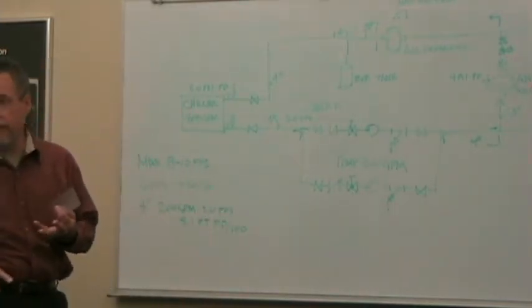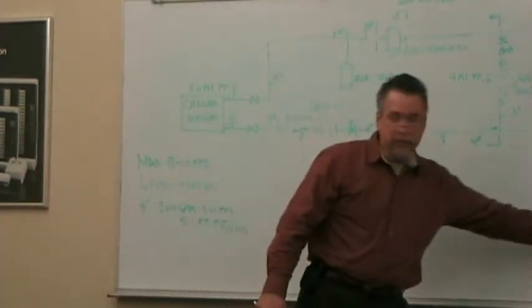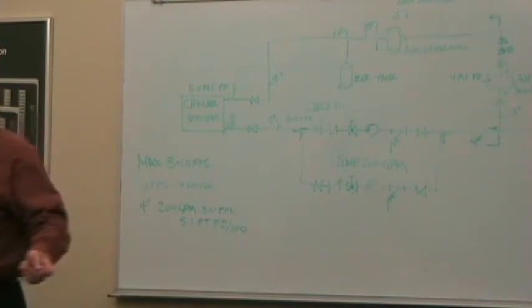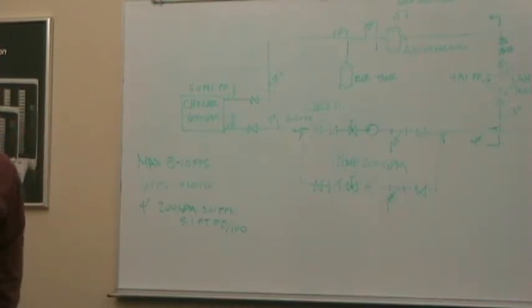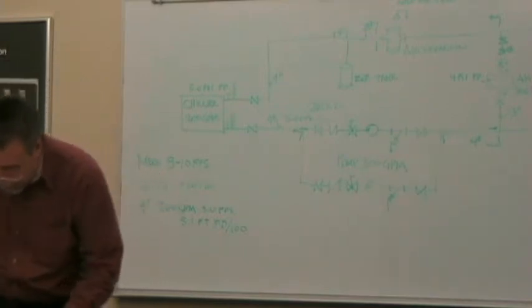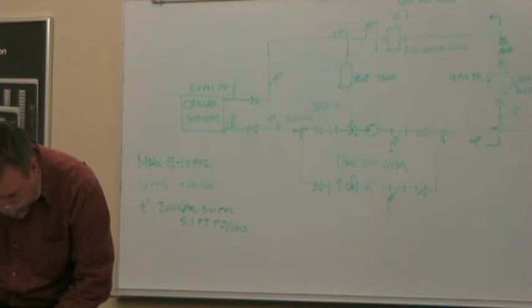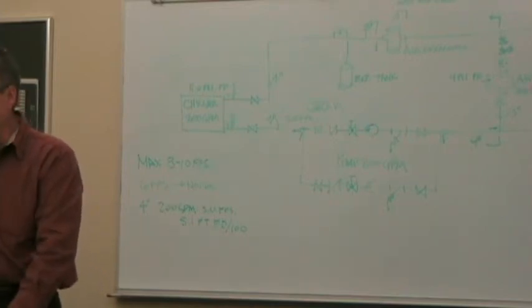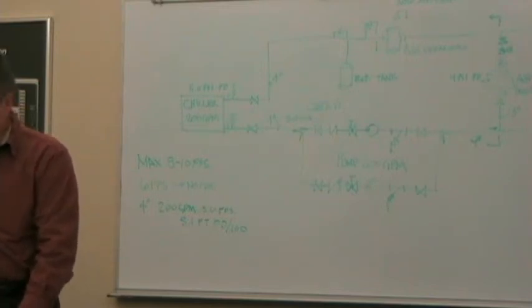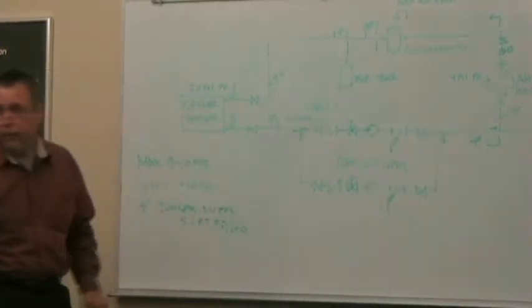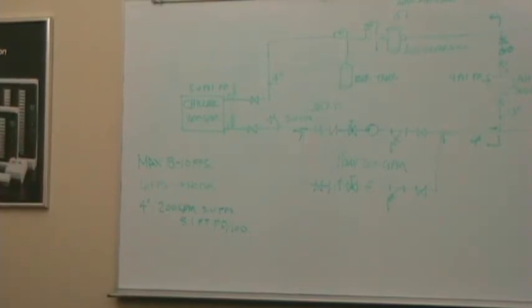Well, I can size the pipe on the C factors of C100 or C150. C150 is clean, brand new pipe. The number I put up here is about a C130. C100 being at the end of its life, with very rough surfaces. So what the Cameron book tells me is, to give you an example, 4-inch pipe, brand new, is 2.25 feet per 100 at 200 gallons a minute. At C130, which is medium roughness, it's 5 feet per 100. So because I'm conservative, I've doubled the amount of loss on the pipe.